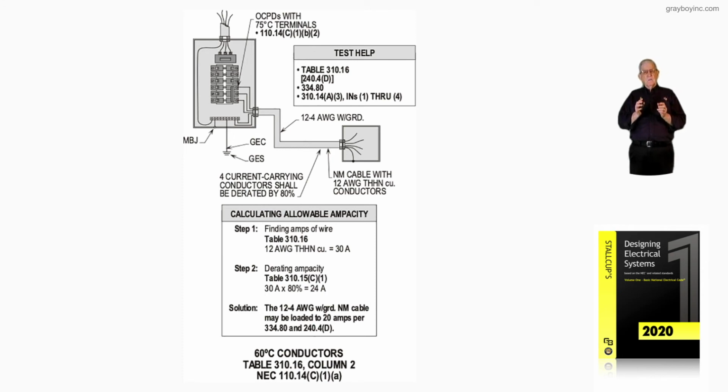You would have to account for that. So harmonics, any type of load like that gives us trouble, inductive loading. Now, if you had 16 amps on L1, L2, and L3, 50% of 16 is 8, so anything above 8, you're current carrying on a Y system with that neutral. And so that's what you got to determine, and that's what we have in that illustration.